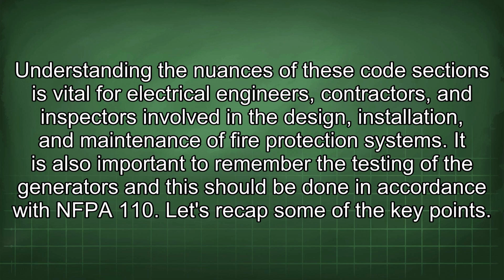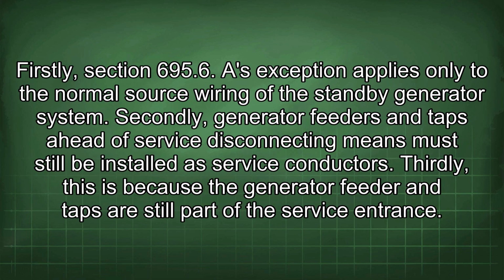It is also important to remember the testing of the generators, and this should be done in accordance with NFPA 110. Let's recap some of the key points. Firstly, Section 695.6.A's exception applies only to the normal source wiring of the standby generator system. Secondly, generator feeders and taps ahead of service disconnecting means must still be installed as service conductors. Thirdly, this is because the generator feeder and taps are still part of the service entrance.